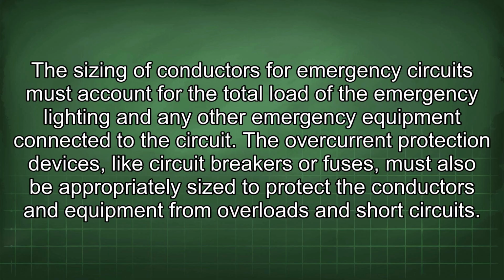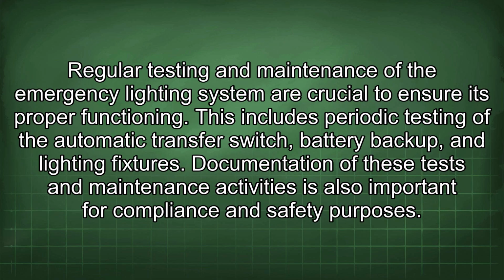The sizing of conductors for emergency circuits must account for the total load of the emergency lighting and any other emergency equipment connected to the circuit. The overcurrent protection devices, like circuit breakers or fuses, must also be appropriately sized to protect the conductors and equipment from overloads and short circuits. Regular testing and maintenance of the emergency lighting system are crucial to ensure its proper functioning. This includes periodic testing of the automatic transfer switch, battery backup, and lighting fixtures. Documentation of these tests and maintenance activities is also important for compliance and safety purposes.